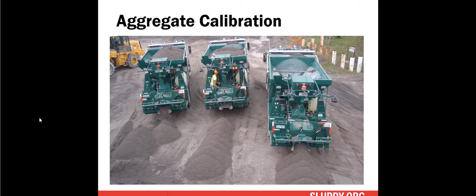I mentioned before about the advantage of some of the newer machinery and the auto calibration process. This is a neat example that shows one operator. You have 3 drivers. We've got one operator calibrating 3 machines at the same time. Because they have an automatic shutoff, in this scenario, he's just making sure that everything is set right. We've started them at different times, so they're going to end. He can collect his data.